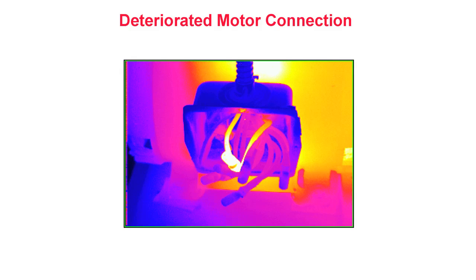Because thermography provides real-time data, this problem is identified in seconds without having to go through the time-consuming and destructive process of disassembling the taped connections. Correcting this loose connection prevents unscheduled downtime and can extend the life of the motor by eliminating voltage imbalances, which increase motor operating temperature.